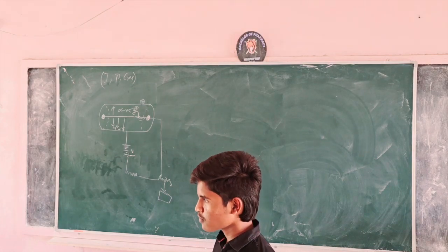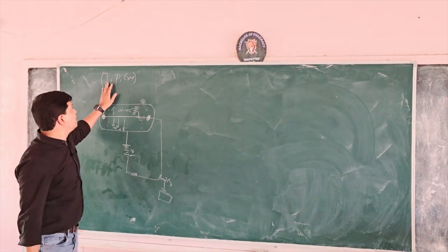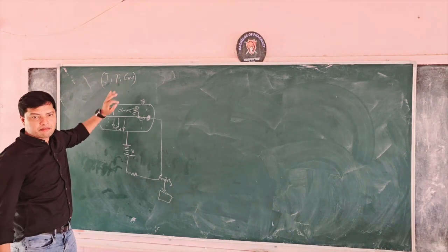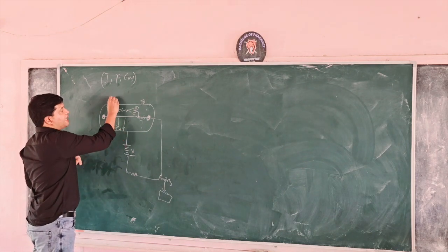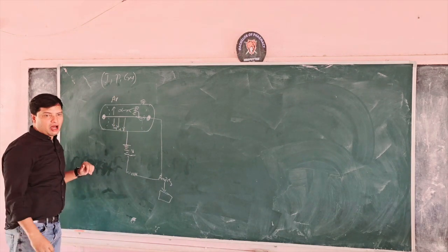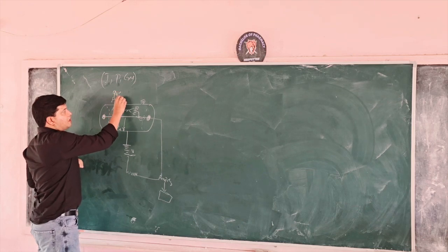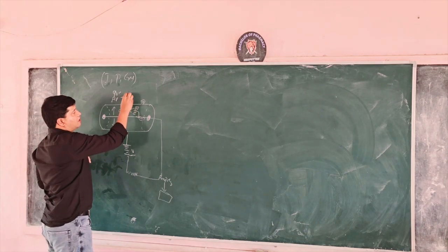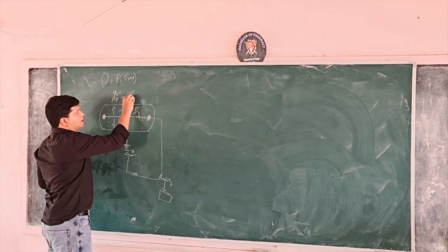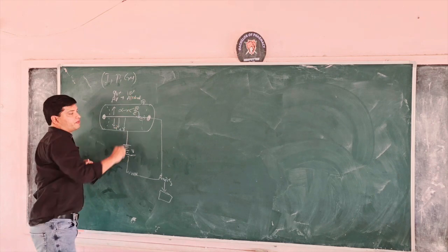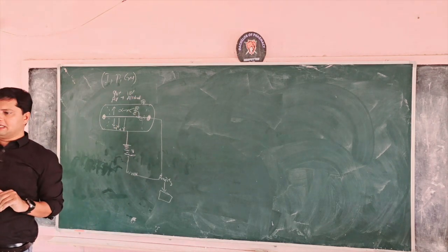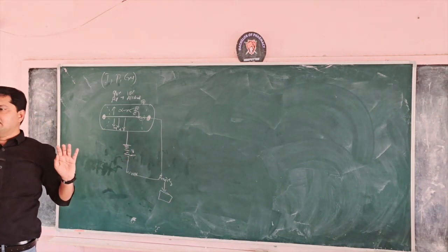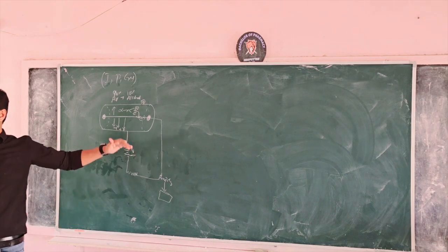Thank you, sir. That is the difference between the ionization, proportional and Geiger-Müller chamber. Here I said gas. The gas used is an inert gas, argon, which is 90%, plus we use the vapor of alcohol, ethyl alcohol or methyl alcohol, that is your 10%. Why alcohol is used, I will tell you later. It is acting as a quenching agent. What is that quenching agent? We will try to see later.